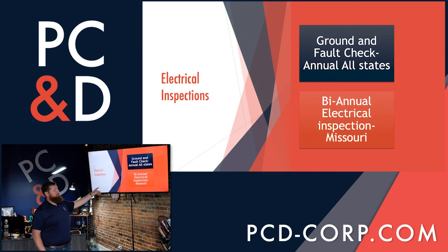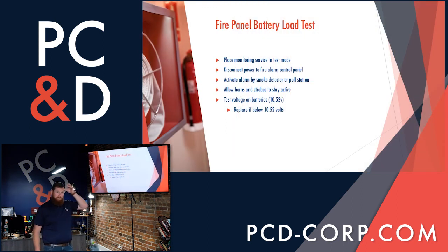Again, on an annual basis, we want to test the GFI and receptacles throughout the entire building and document them. If any issues are in place, it needs to be resolved and documented. With the exception of Missouri, in which case every 2 years a licensed electrician must come to your building, take a sample portion of your outlets, test them, and then they will send off their report to the state for approval.